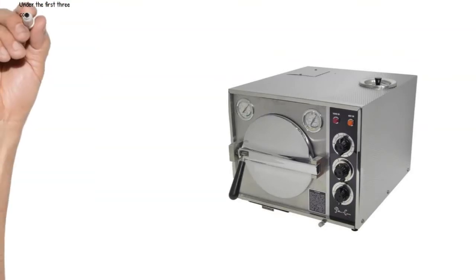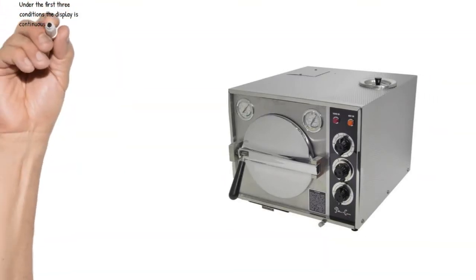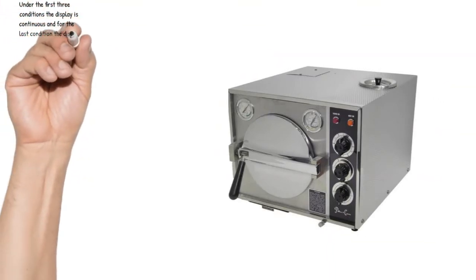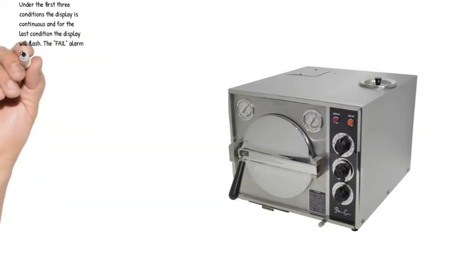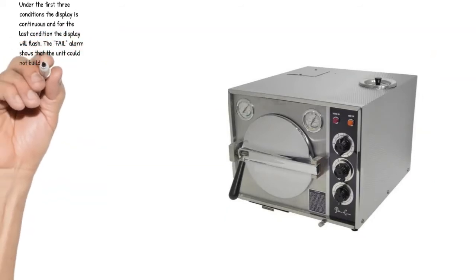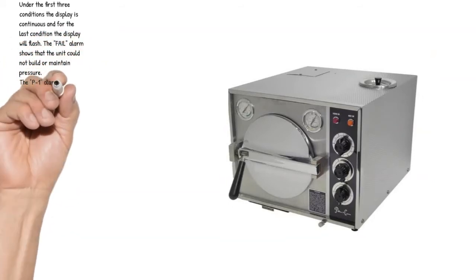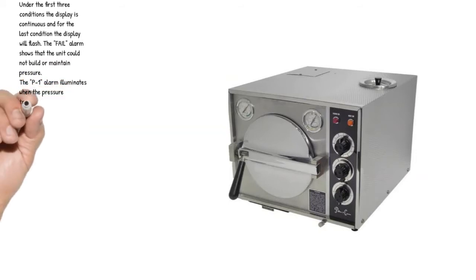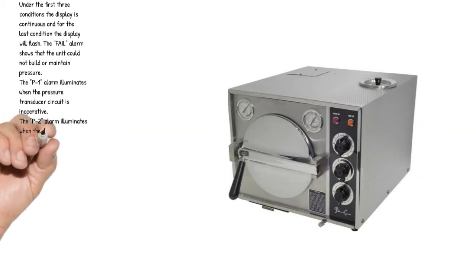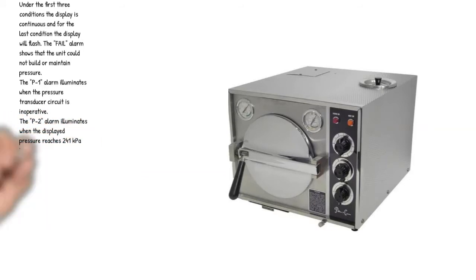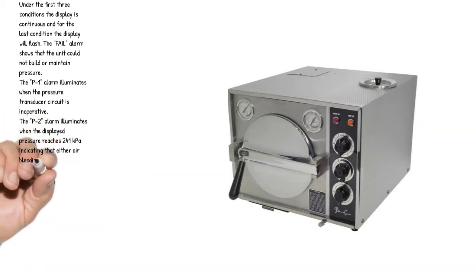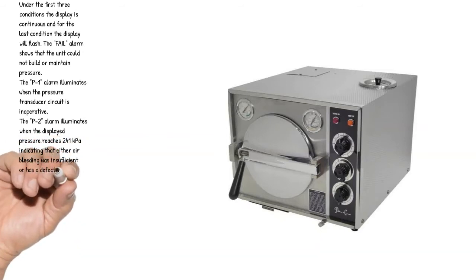Under the first 3 conditions, the display is continuous, and for the last condition the display will flash. The fail alarm shows that the unit could not build or maintain pressure. The P1 alarm illuminates when the pressure transducer circuit is inoperative. The P2 alarm illuminates when the displayed pressure reaches 241 kPa, indicating that either air bleeding was insufficient or has a defective steam or pressure sensor.